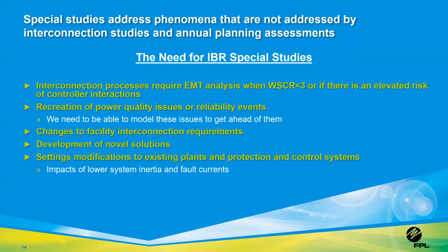We also perform studies for disturbance analysis. Fortunately, we haven't had any major events, nothing that would necessitate a NERC event report or anything like that. But even when you have a single plant misoperate and there's minimal reliability risk to the bulk electric system, you still need to perform a study. We need to collect data. We need to fully understand what happened. We need to identify mitigations and roll them out to all applicable units. And we also need to assure that our studies can capture this issue going forward.